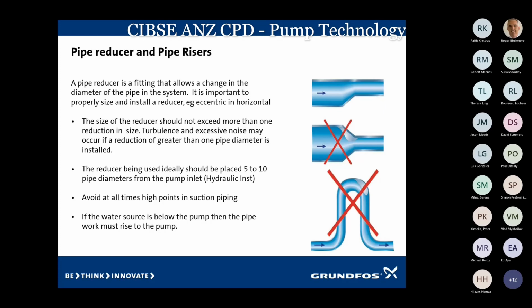Avoid high spots. I remember going to a building in Wellington, and they said, "Oh, your pump won't run, we can't get it to run." And I climbed up into the ceiling to have a look, and it was a big U shape like this, and they had the pump sitting in the leg. Somebody had been in and serviced a radiator down the bottom, and they bled the system, but they couldn't bleed this point because there was an airlock, and the pump was just running, but there was nothing happening.